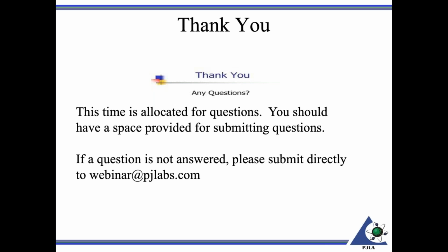In the reference material area, I can kind of read the content of reference material certificates and product information sheets, which shall include the following. Sometimes you might get an actual reference material certificate in terms of an analysis, but you also get a product information sheet that might have safety information on it, or maybe storage and disposal and so forth. So in general, you've got to have a title. It's got to be clear as to what it is. A unique identifier of the reference material itself, the name of it if required, and the name and contact details of the RMP, the producer. What's the intended use? What is this going to be used for? That could be in the product sheet, or it could be in the certificate.